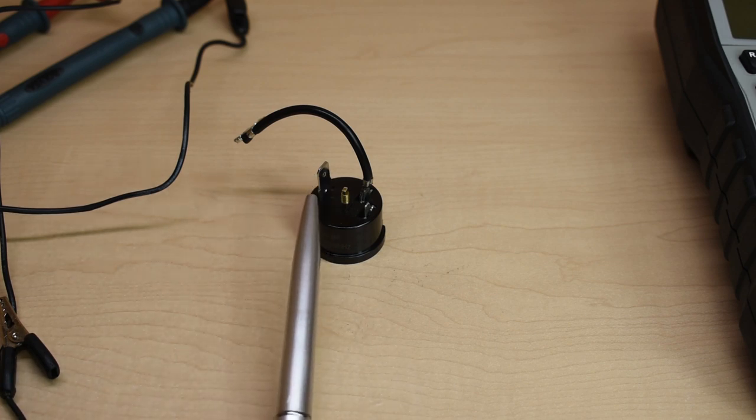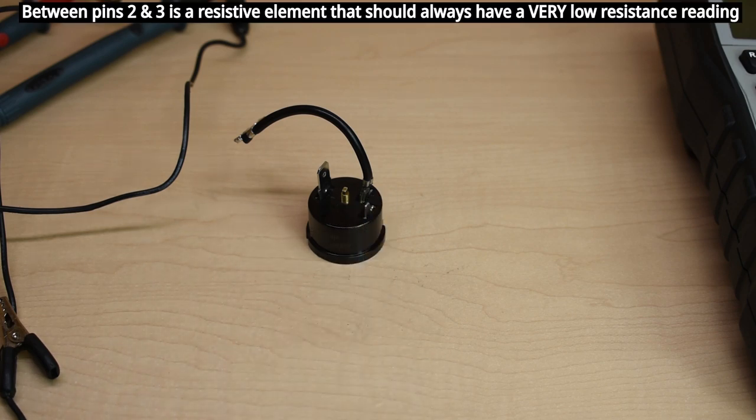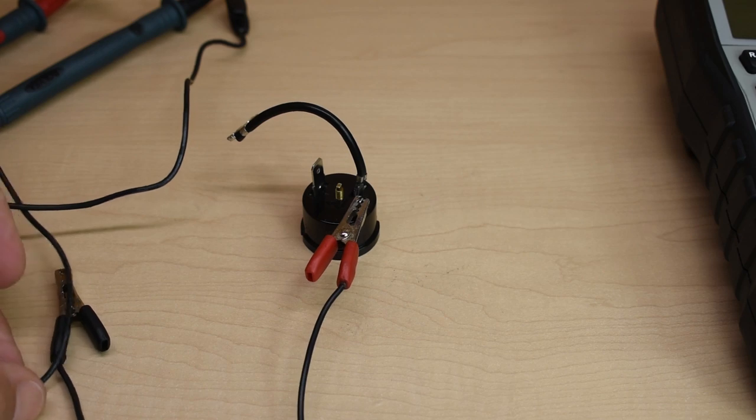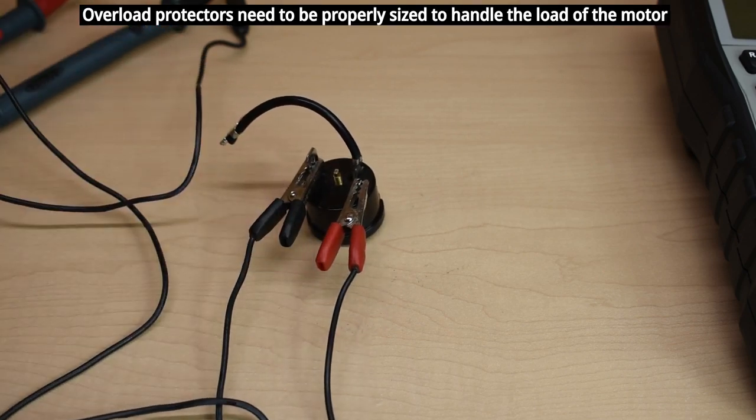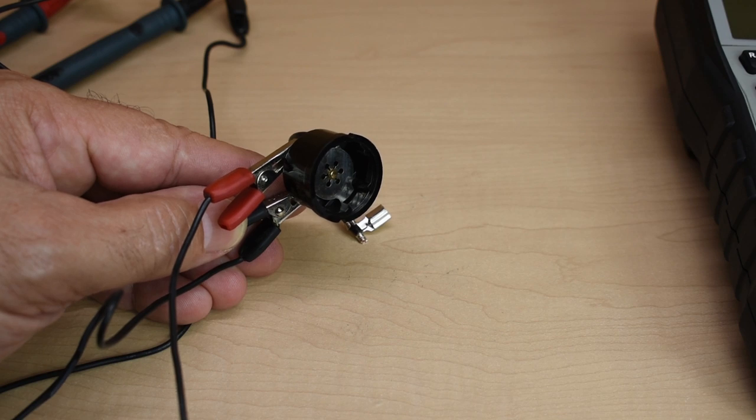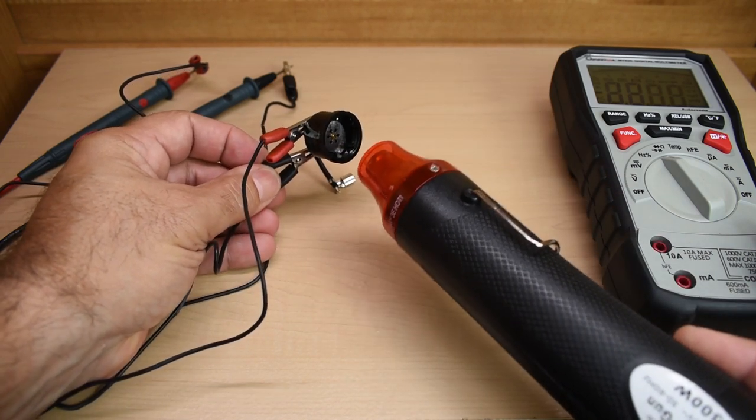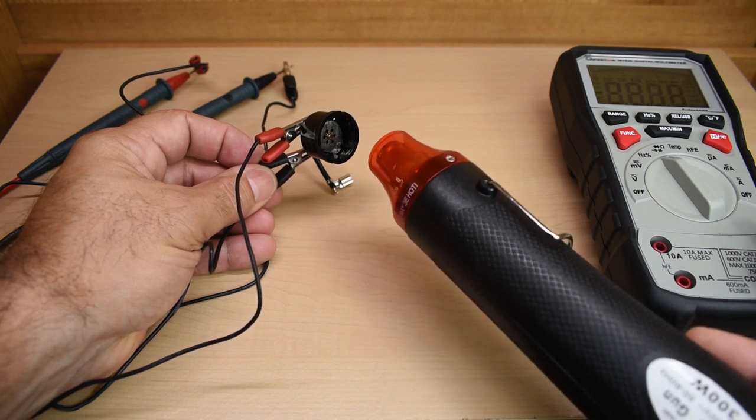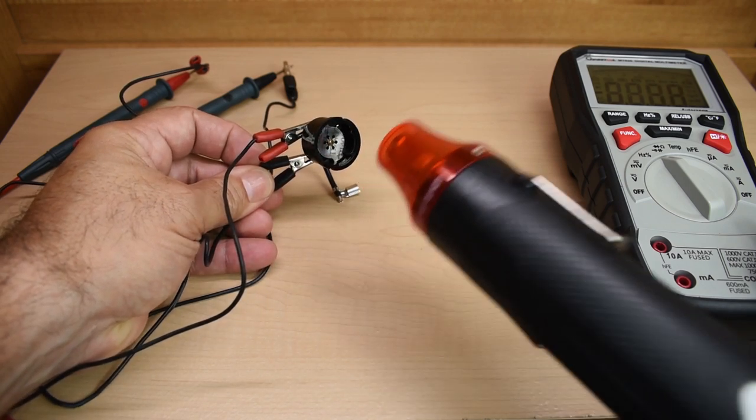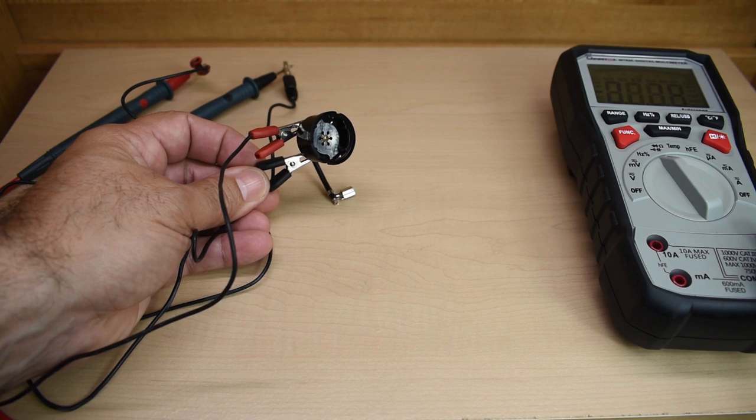When an electric motor is cold, you should have continuity between pin 1 and pin 2. If you don't, that's going to indicate a fault with the overload protector. For this demonstration, I'm going to connect this up to my digital multimeter, leave it on a continuity alarm setting. Then I'm going to take my heat gun and direct it right at that disc. When the sound on my digital multimeter turns off, you're going to know that the circuit has opened. And as soon as it cools down, it'll pop back into position and current will flow again. There it is.